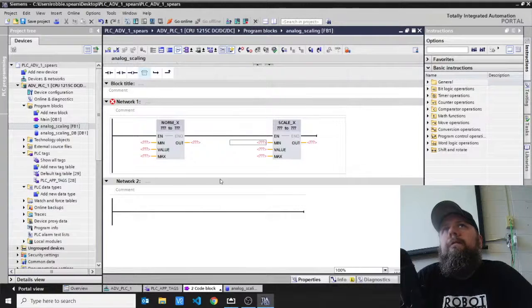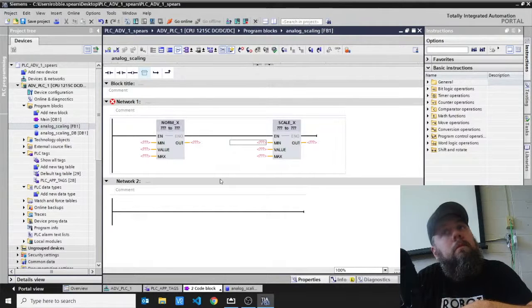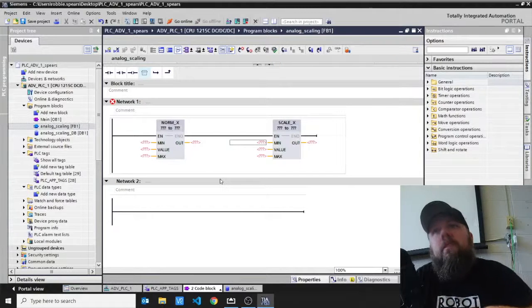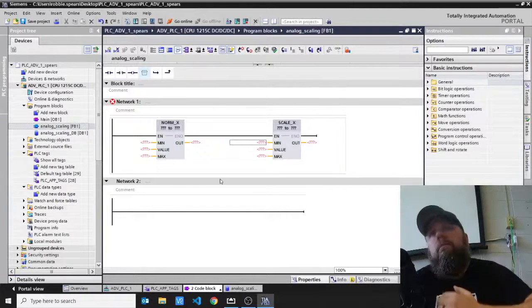So if I had a minimum of 0, a maximum of 100, and I gave you 25, it'd be 0.25, right? And then if I wanted to scale that between 0 and 200, then I would just multiply that 0.25 times that 200, get 50, so 50 would be the same proportion in the other range. So that's going to take things from one range into another, okay?